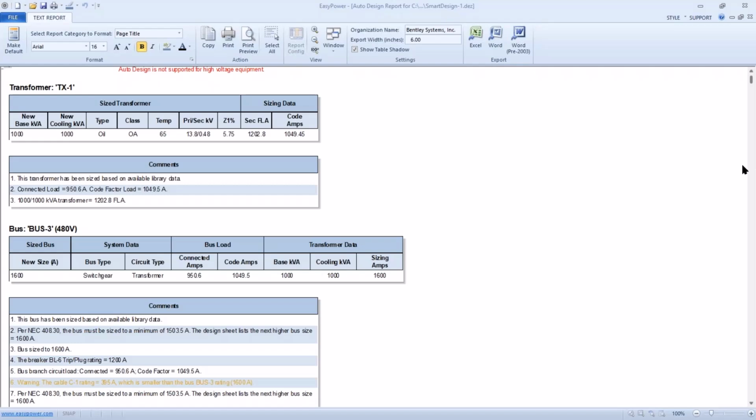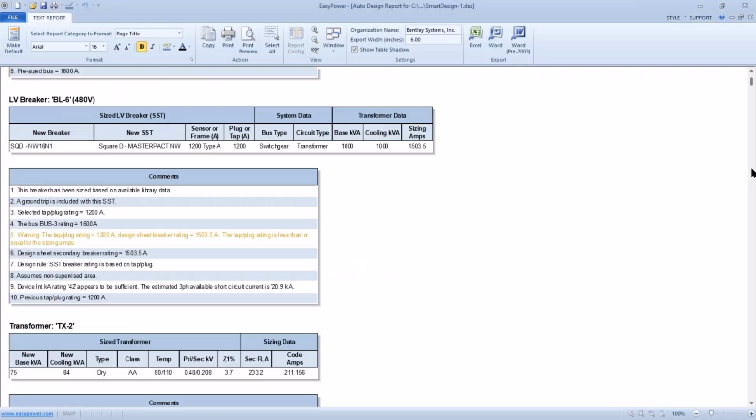Now, not all this is going to be perfect. And so where it throws an error, it gives me a warning that there was 1500 amps rated, and we're tapping it equal to the sizing on the amps. So a human may want to check this out.